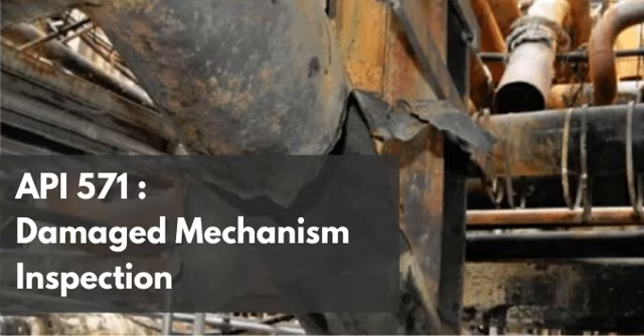Okay, let's start with copper alloys. For copper alloys, the first line of defense isn't actually looking at the metal itself. It's looking at the chemistry. You mean operational monitoring, like checking the pH and ammonia content of water draw samples. Exactly. It functions almost like running blood work on the heat exchanger. You are constantly analyzing the cooling water or the process fluid.